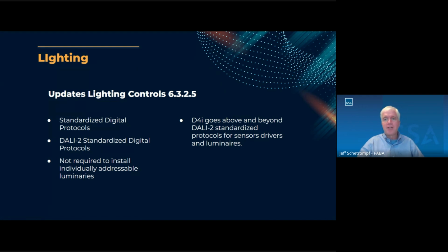All right, so lighting controls had a handful of updates. First off, before we get too far here, we do not require controls involving individually addressable luminaires or fixtures. However, we do recognize that such controls may have a beneficial role on some projects, so we're including discussion on DALI 2 and D4i. DALI stands for Digital Addressable Lighting Interface. It's a communication protocol across the lighting control system. Some of you out there probably worked on previous DALI projects, maybe under ARRA. You probably have a few horror stories that we don't want you to share here today.